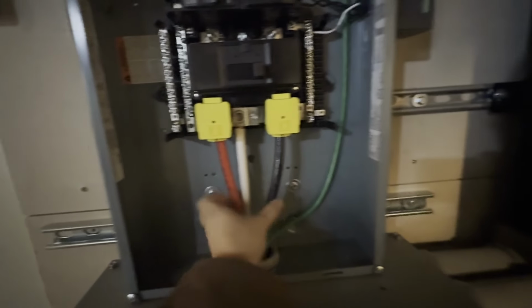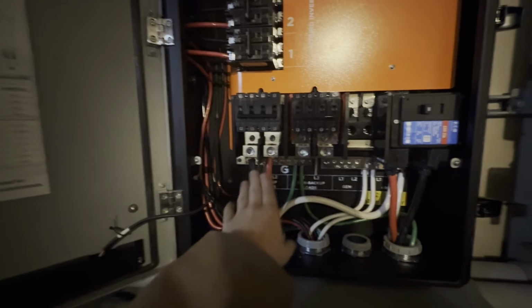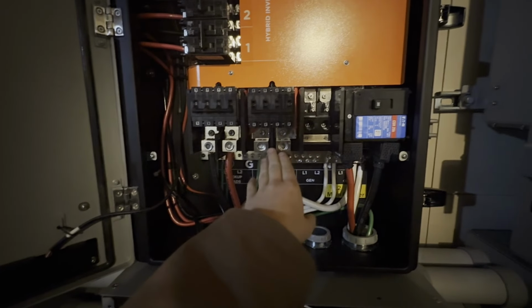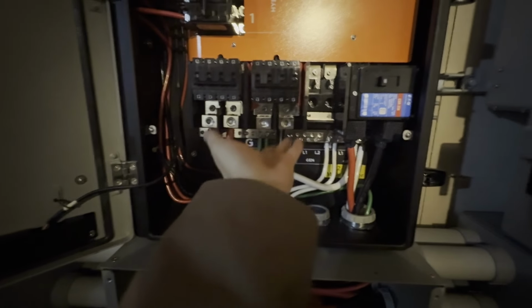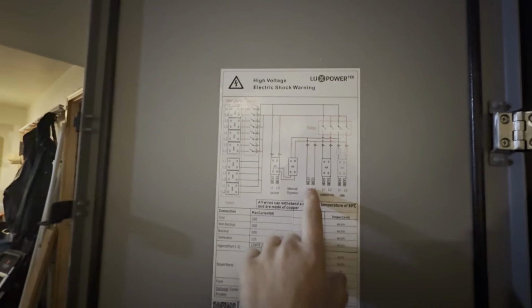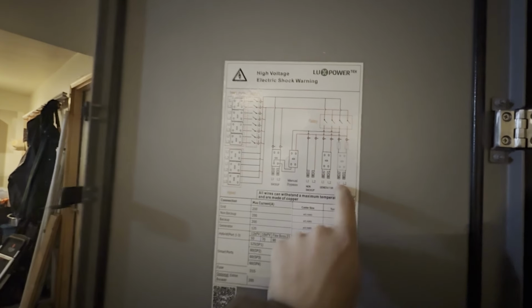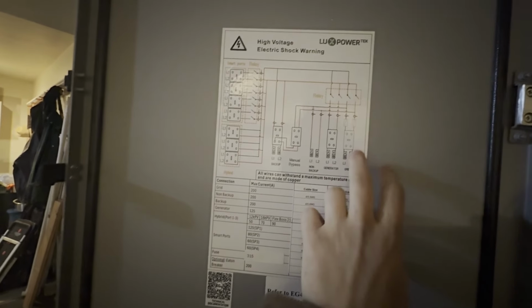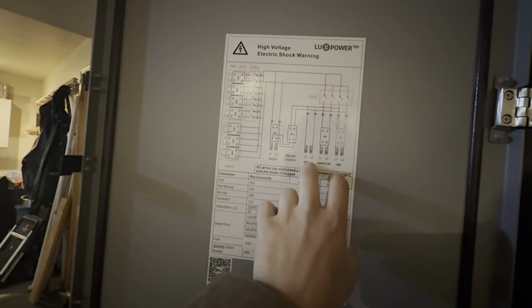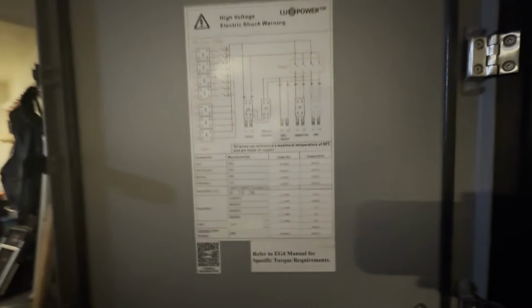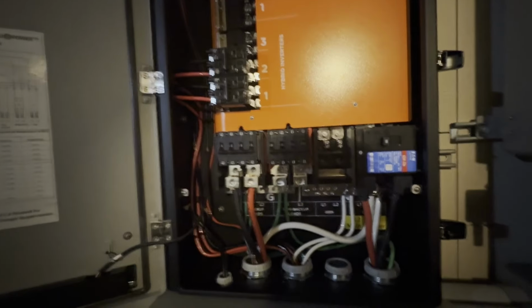This is where the power comes in from the mid, so from the Grid Boss, that's the backup loads port here, and this is the non-backup loads port. I'm not going to use that at all, so nothing will ever be connected to those. The non-backup is connected always straight to the grid, and that's it. It's not ever connected to the inverters or anything like that. So if the grid is down, the non-backup port just doesn't have power. I don't have a need for that with my setup, so nothing's connected to it.